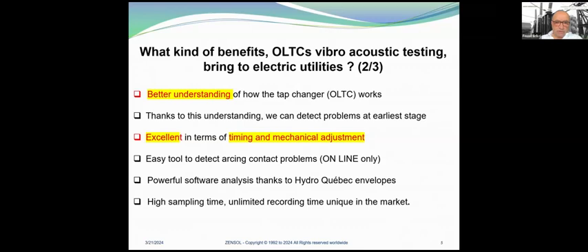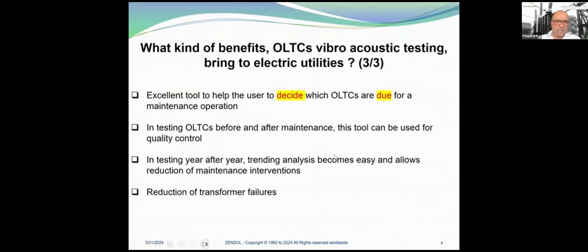We have powerful analysis software, thanks to Hydro-Quebec envelopes that simplify the analysis. We have a high sampling rate and unlimited recording time, unique in the market. It's an excellent tool to help the user decide which OLTCs are due for a maintenance operation. By testing OLTCs before and after maintenance, this tool can be used for quality control. In testing year after year, trending analysis becomes easy and allows a reduction of maintenance interventions. And of course, our goal is to reduce transformer failures.